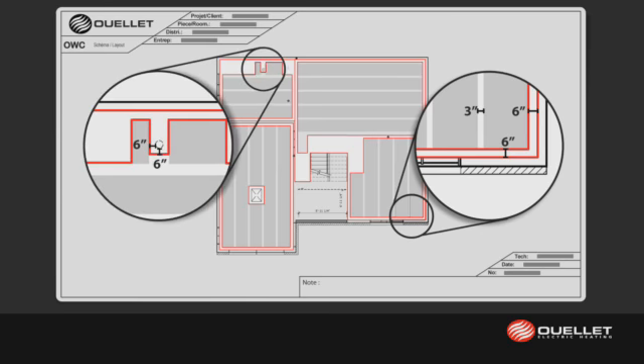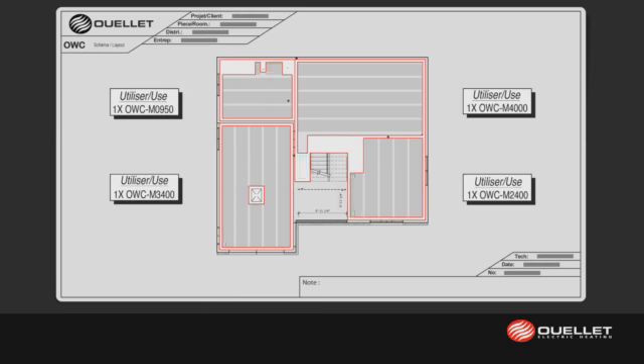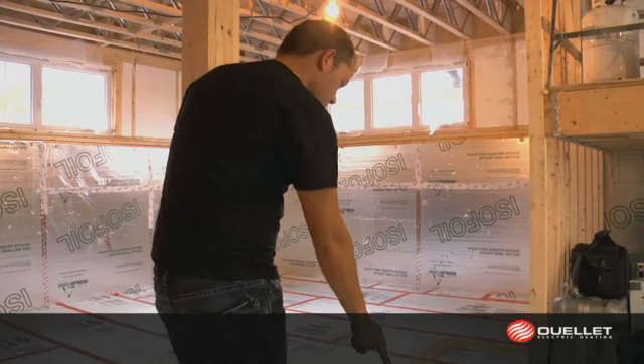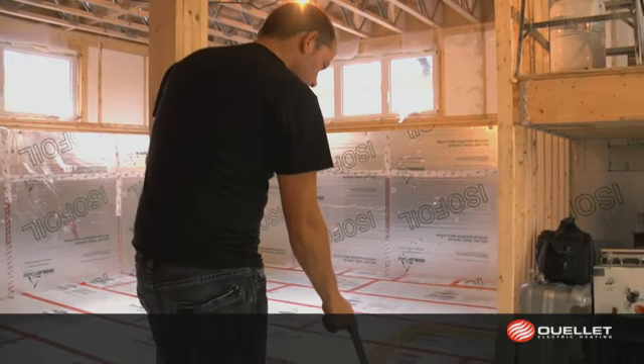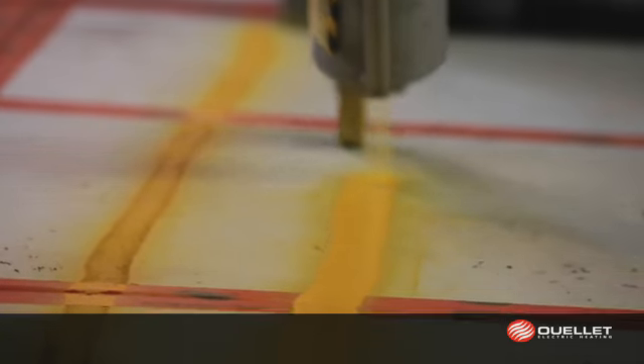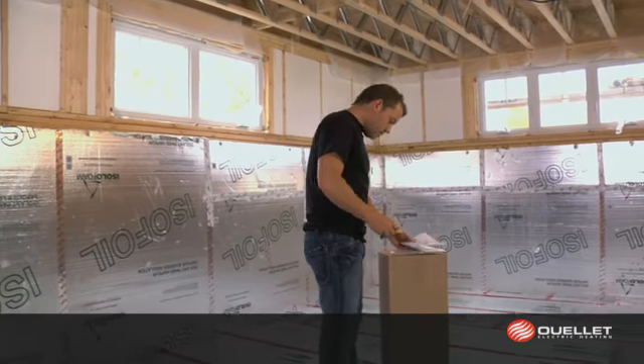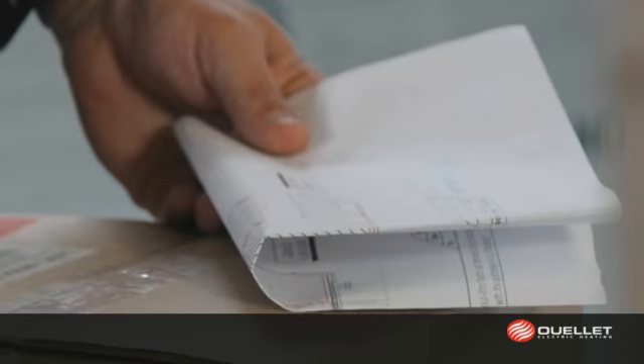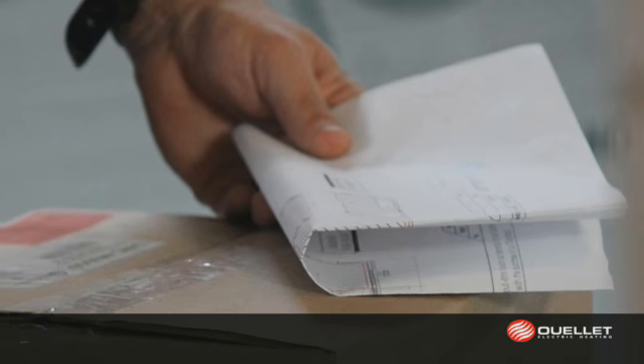The layout should include buffer zones that are easily accessible at the end of the installation, where you can place any excess cable if necessary. With the help of your plan, use a marker or spray paint to trace the perimeter of the net heated area. Before beginning the cable installation, make sure you have the appropriate mat size by checking the information found on the product label.